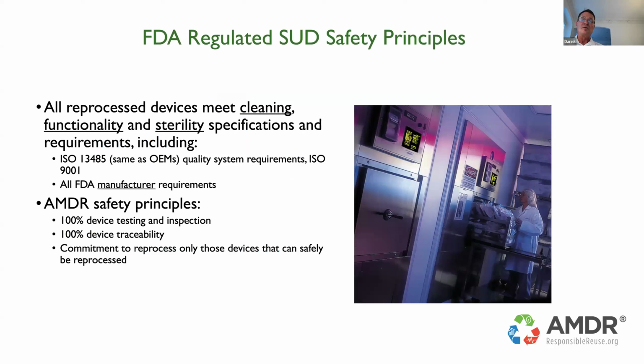And so our safety principles beyond meeting medical device manufacturer requirements are that we test or inspect 100% of the devices that we reprocess. An original manufacturer will give you back a sampling. We test or inspect everything. We trace or track everything on the device. I don't know if you can see it, but we'll have tracing barcodes or some way to track it. And obviously, we can only reprocess those things for which we have a cleaning and sterilization validation demonstrating the product is safe and effective.